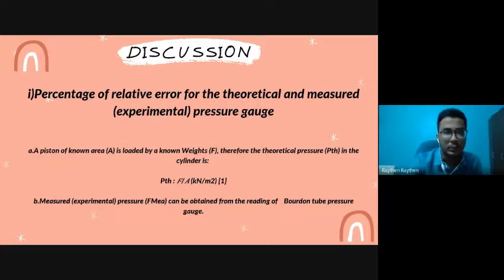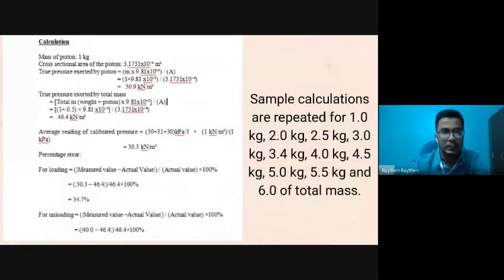First, the percentage of relative error for the theoretical and measured experimental pressure gauge. A piston of known area is loaded by a known weight F, therefore the theoretical pressure in the cylinder is F over A, which has the unit kilonewton per square meter. A measured experimental pressure, F measured, can be obtained from the reading of the Bourdon Tube Pressure Gauge. So next, this is the calculation part.